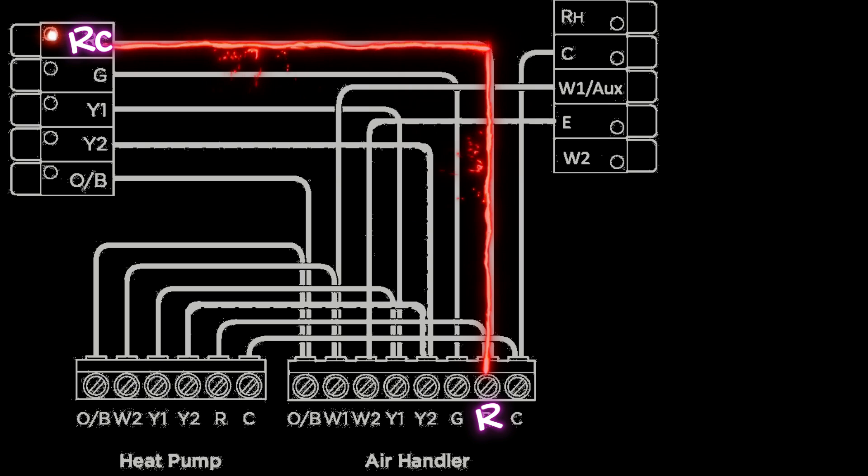Now keep in mind as we go through this, the color of the electricity you see flowing on the wire in the schematic is going to be the color of the wire we typically use to make these connections. So in this example, we have a red wire coming off that R terminal on the air handler going into the RC terminal on our thermostat.